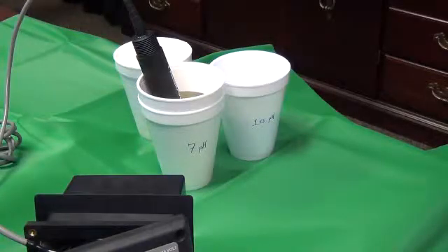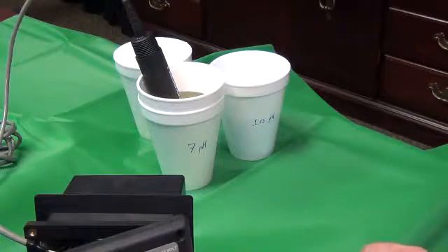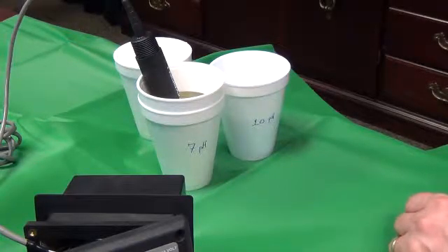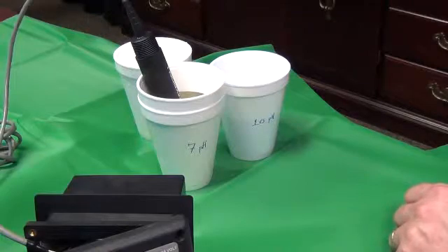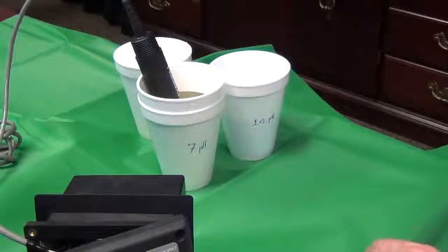So let's now simulate a situation where we're going to see a rising pH, and we will treat this with the pumping of acid to lower the pH back down to our desired set point of 7.0 or neutral pH. When we have a rise and lowering in pH, we also have a change in the value of the 4 to 20 milliamp signal on a linear basis. So as we go up in pH, becoming more alkaline, the 4 to 20 milliamp signal increases. Conversely, as we pump, in this case, acid to lower the pH back down to 7, the 4 to 20 milliamp signal will reduce in value.